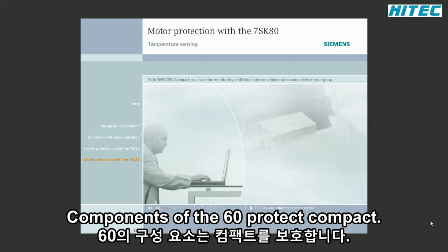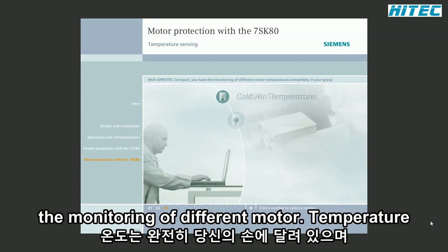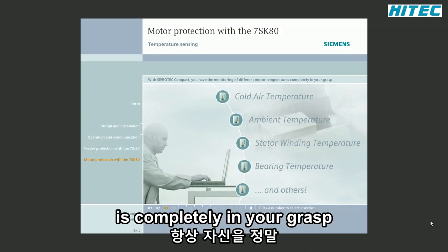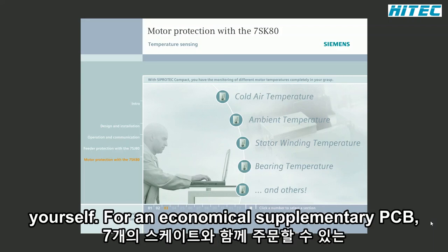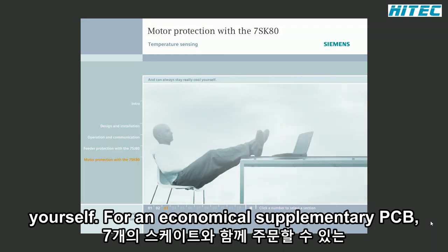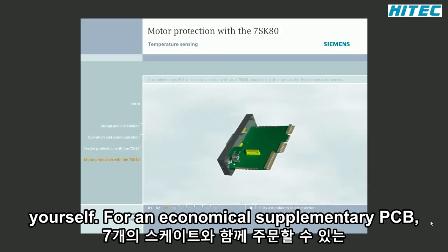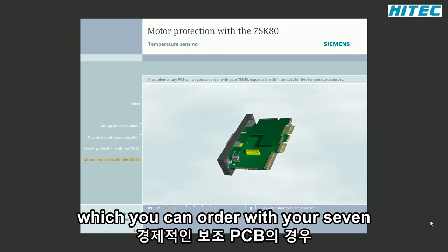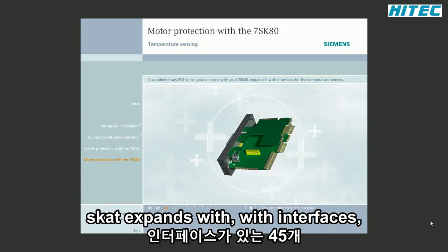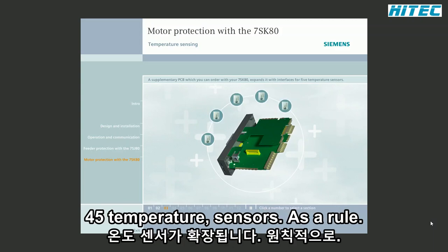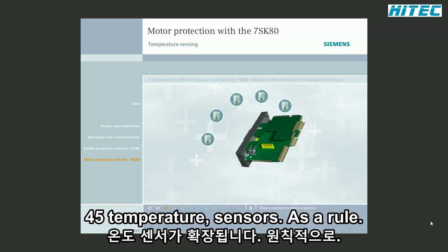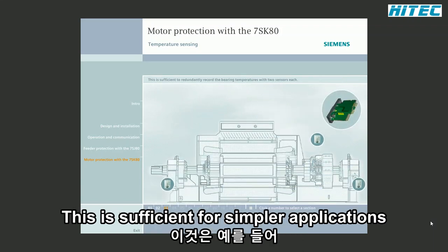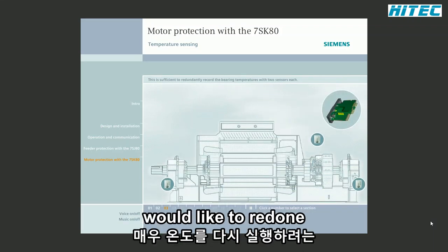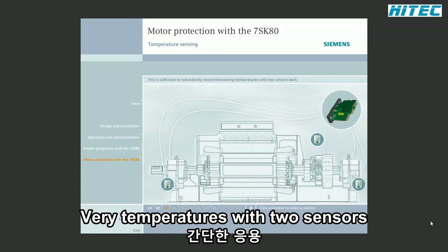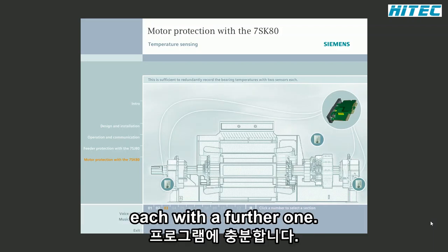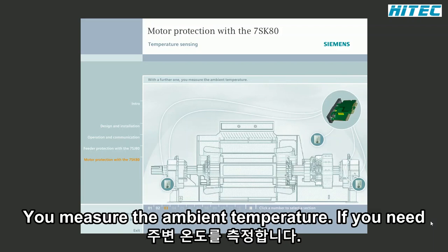With SIPROTEC Compact, you have the monitoring of different motor temperatures completely in your grasp and can always stay really cool yourself. For an economical supplementary PCB, which you can order with your 7SK80, expands it with interfaces for 5 temperature sensors. As a rule, this is sufficient for simpler applications in which you, for example, would like to redundantly record the bearing temperatures with 2 sensors each. With a further one, you measure the ambient temperature.